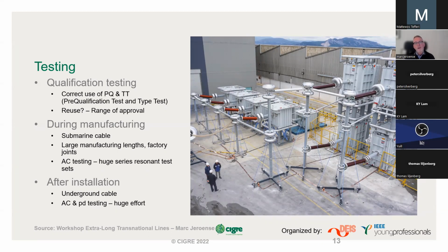What I think will happen in future is that instead of always asking for a new PQ test and type test, one might make use of the range of approval, meaning I, as a manufacturer, could say I have already done my type test two years ago on another project, with the same kind of cross-section and voltage rating. Can I use that in your project, dear customer, within the range of approval? I think it would help the industry if, in a responsible way, we use that tool of range of approval to avoid a further explosion of testing. Testing is important, but you have to be careful not to overdo it. It's a very delicate balance, I can say.